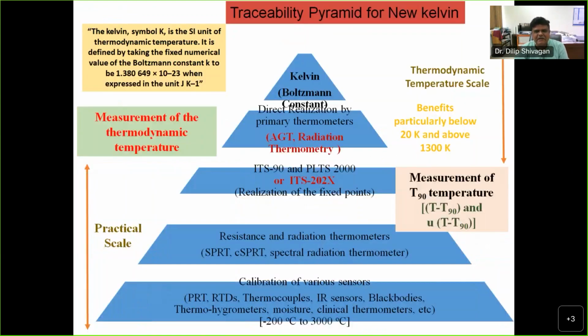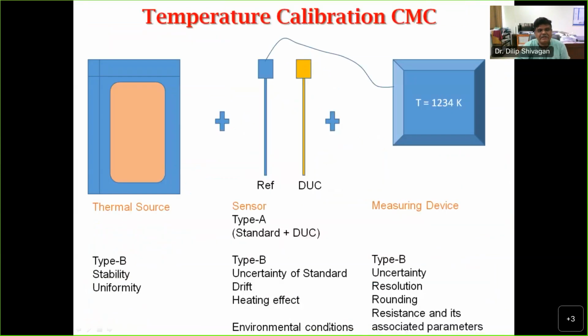So as I said, this will be a new primary standard, which is acoustic gas thermometry. And for high temperature, we are also simultaneously going for radiation thermometry with metal carbon eutectic fixed points, so that from the lower range to the higher range, we can have direct traceability to support our present measurements from -200 to 3000 degrees Celsius. So now we will come to temperature standards. What are the requirements, and how are measurement uncertainties and CMCs involved?